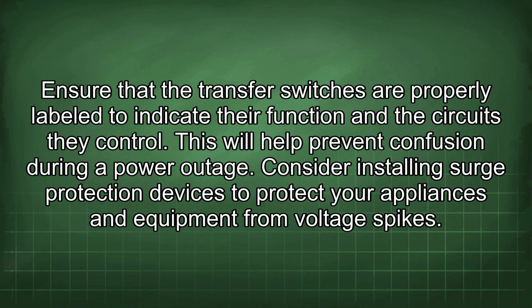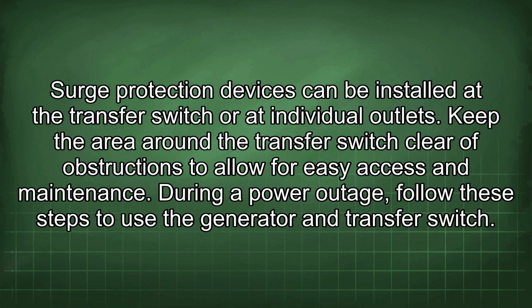Ensure that the transfer switches are properly labeled to indicate their function and the circuits they control. This will help prevent confusion during a power outage. Consider installing surge protection devices to protect your appliances and equipment from voltage spikes. Surge protection devices can be installed at the transfer switch or at individual outlets. Keep the area around the transfer switch clear of obstructions to allow for easy access and maintenance.